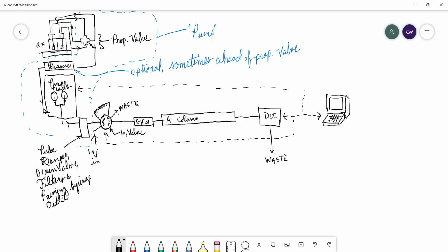Then the analytical column will outflow to the detector. Now, this piece of tubing right here is very important. You want to make sure that you keep this piece of tubing, as well as all the rest of these, as short as possible, but especially this one. Okay? This must be as short as physically possible. And I want you to think about why that could be and post it in the comments below, based on what you know about chromatography. Why would we want this line here after the column to be as physically short as possible?